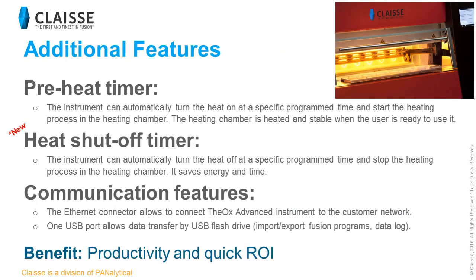To save time, the user can use the preheat timer to start the heating process of the heating chamber at a preset time of day, so the heating chamber is heated and stable when the user is ready to use it — meaning no downtime and higher productivity. Conversely, with this new version, it is also possible to program the time when the heat should be turned off. The user can use this feature before maintenance or to save energy while the instrument is not being used, simply by programming the timer according to their activities.